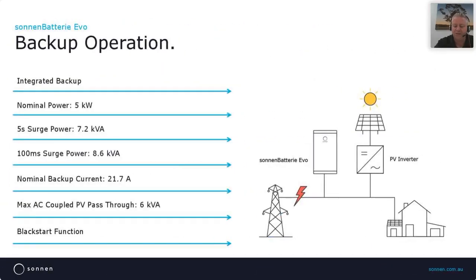The sonnenBatterie Evo has integrated EPS backup functionality. This means no additional connections box or Sonnen Protect unit, again making for an easier installation. The backup supply is a 5 kilowatt continuous and a nominal current of 21.7 amps. It has a surge capacity for 5 seconds of 7.2 kVA and 100 millisecond surge of, say, 8.6 kVA. The higher output enables more circuits to be connected to the EPS supply, meaning the customer can use more appliances when there is a grid outage, and also reducing the time and cost to separate designated circuits in the customer's board. The sonnenBatterie Evo can process 6 kilowatt of AC coupled PV inverter on its backup circuit and an unlimited amount on the grid side.